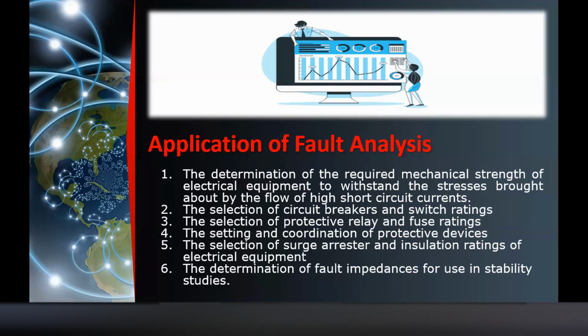The number 4, this is more important, is the setting and coordination of your protective devices. So hindi naman pwede yung i-input mo sa relay mo, no, or yung sa circuit breaker mo, yung mga merong electronic trip unit, isuhulaan mo. So mali 'yon. So you have to rely on your fault analysis and calculation. Kung ano yung makuha mo sa fault analysis, yun ang gagawin mo or isa-set mo sa mga protection devices mo. Number 5, the selection of surge arrestor and insulation ratings. This is more on insulation coordination. And number 6, determination of fault impedances for use in stability studies. Okay.